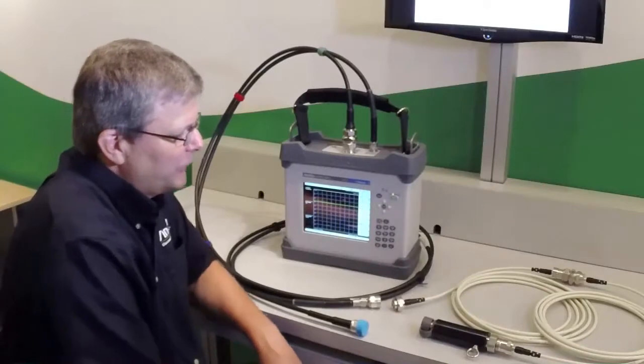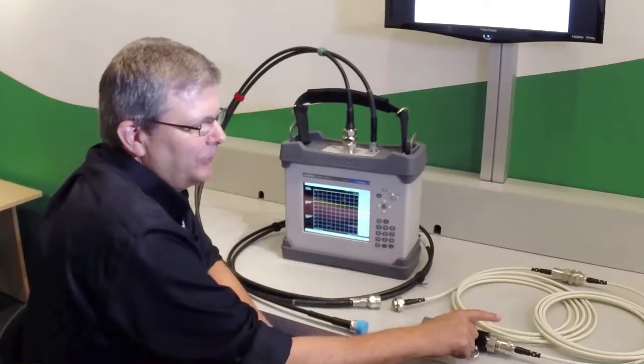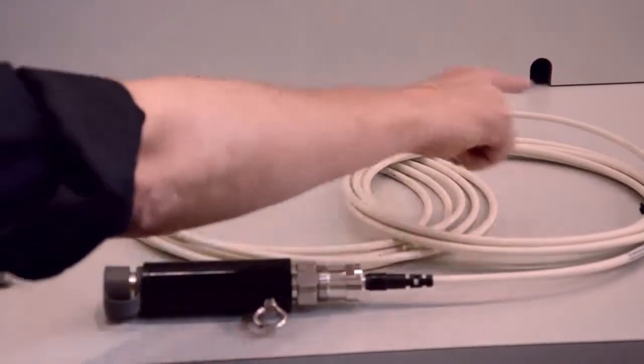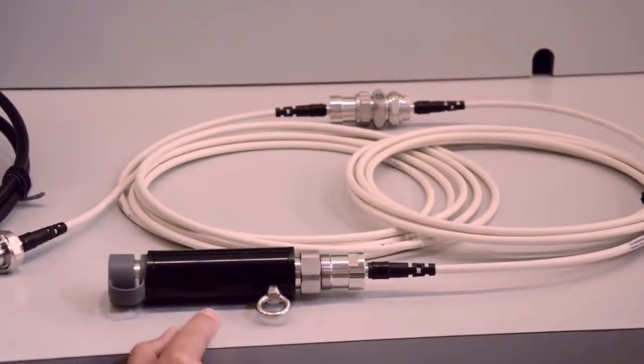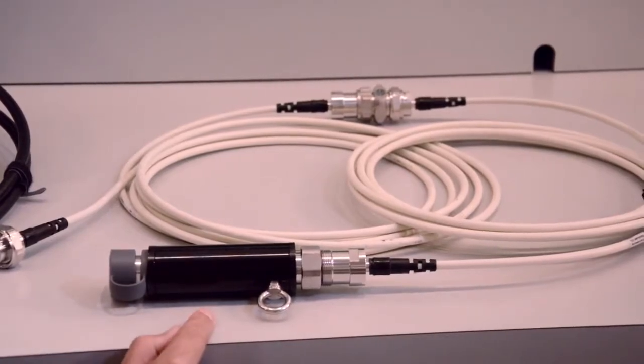The system that we're going to demonstrate on today is two 5-meter cables with a PIM standard installed at the end of the first 5-meter cable and a low PIM termination installed at the end of the cable. In this case, the low PIM termination will be simulating the antenna on the system.